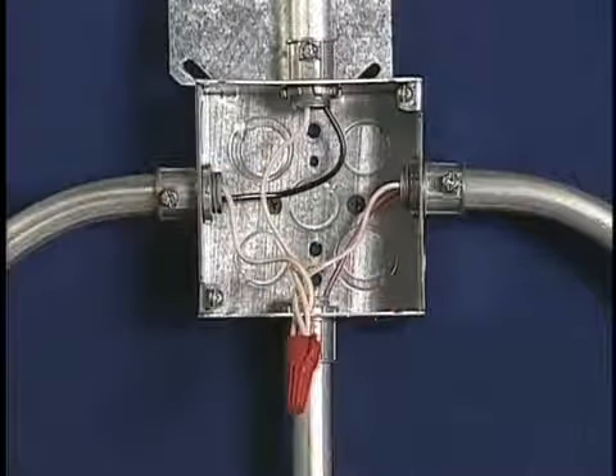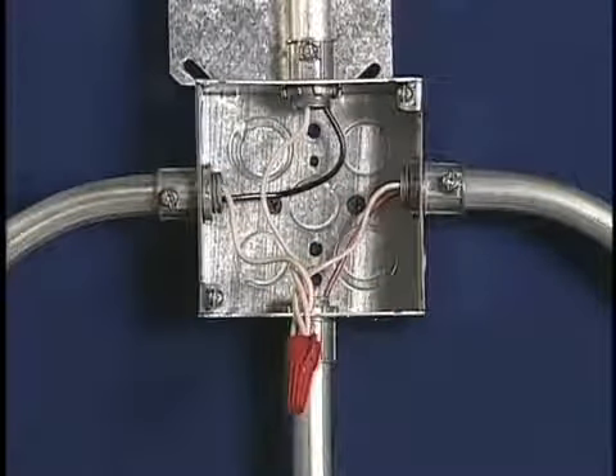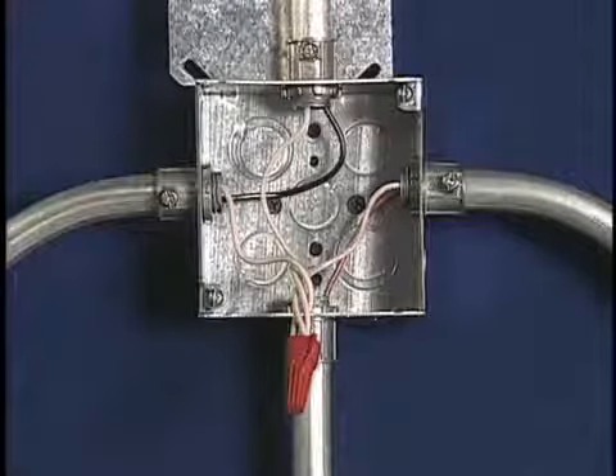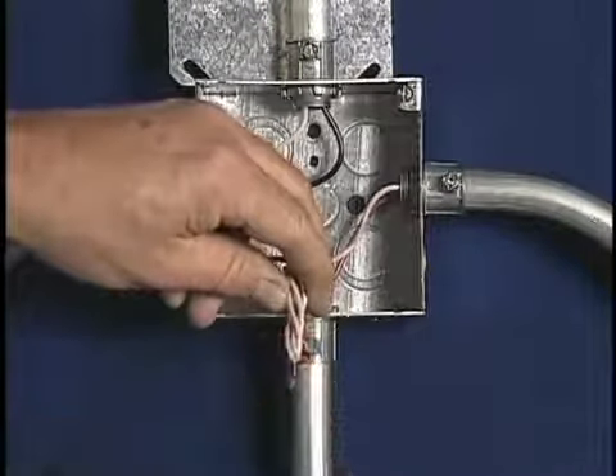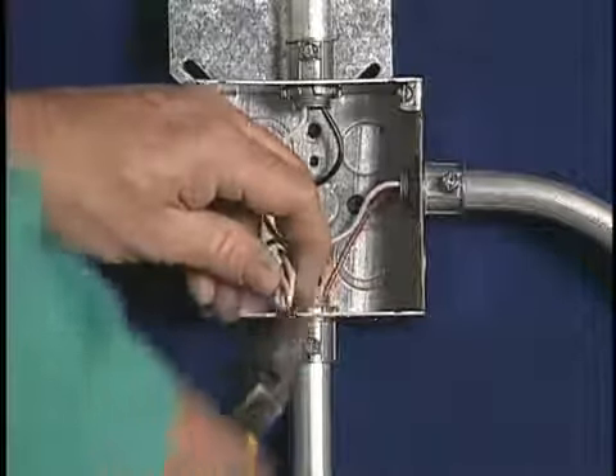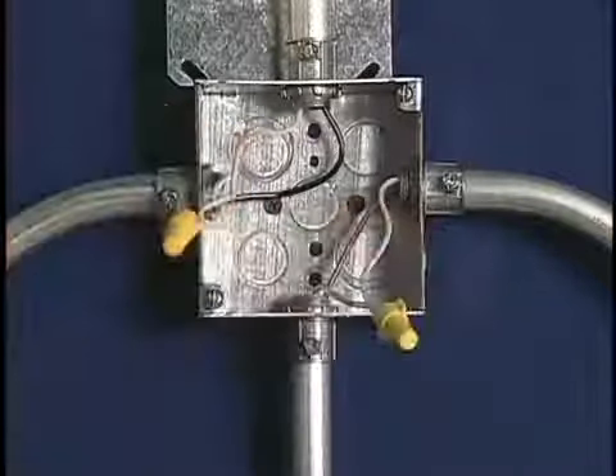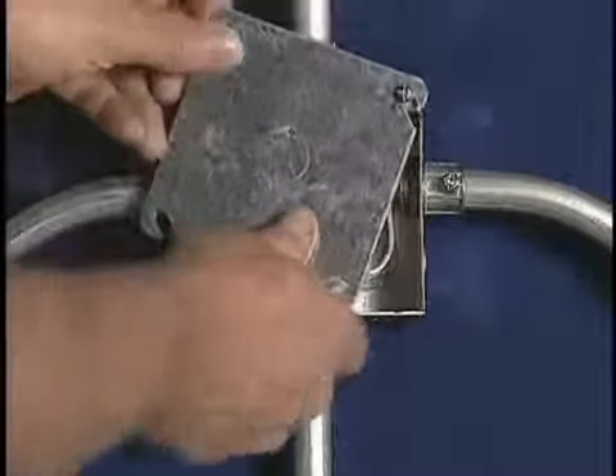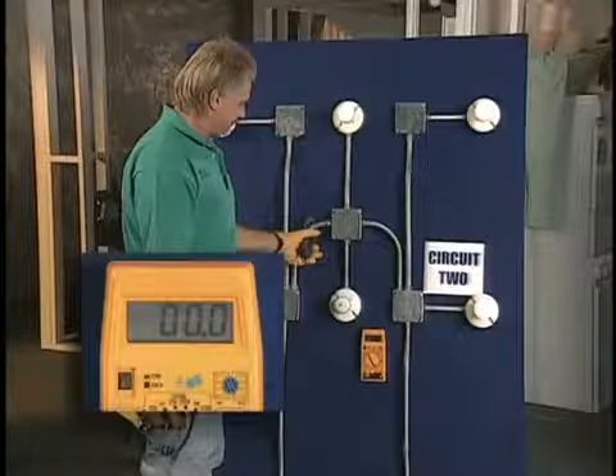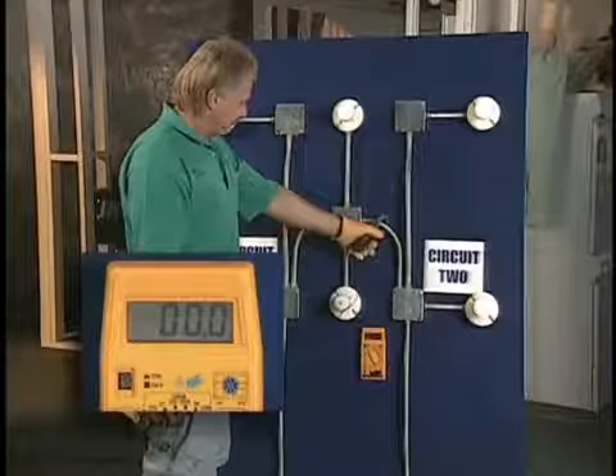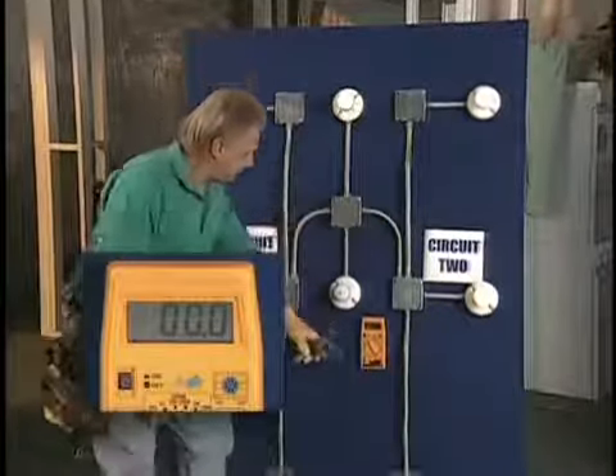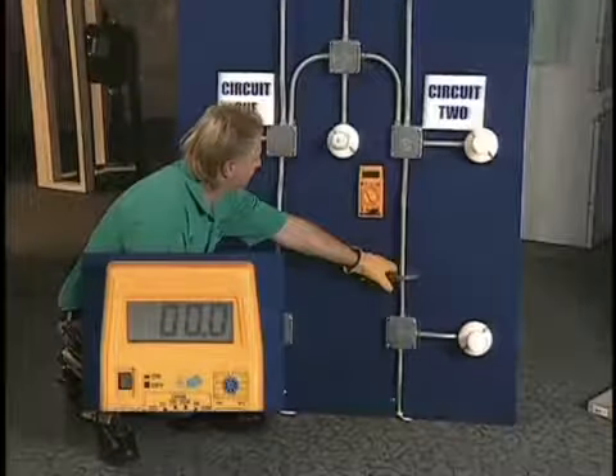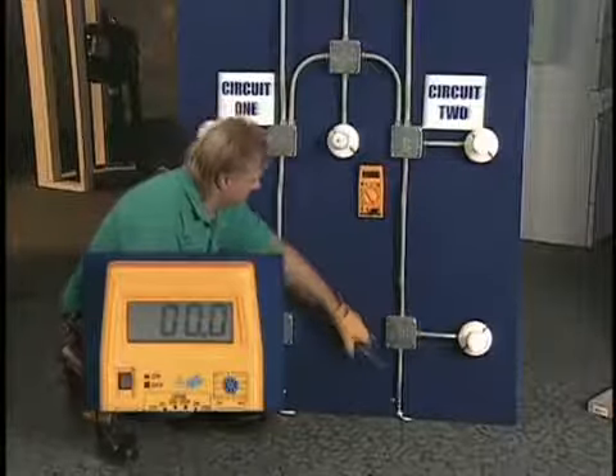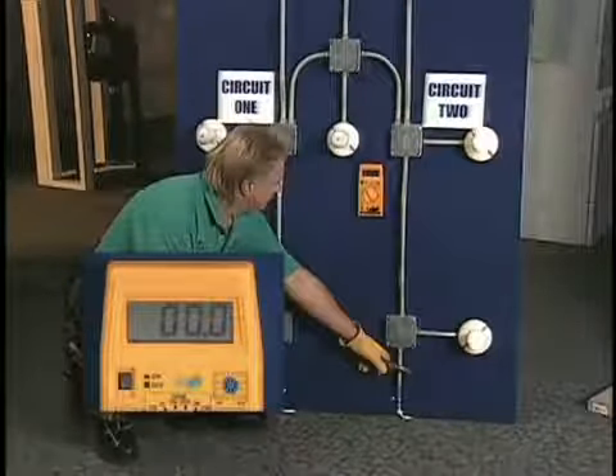Here we see that the neutrals from 2 branch circuits have been connected together. We have found the source of the net currents. Now open the breakers for these 2 circuits to de-energize and correct the error. Now energize the circuit and check the conduits again. No net current. Your school may want you to verify that the previously measured magnetic field levels have decreased. Refer to the original area magnetic field measurements and remeasure with the Gauss meter.